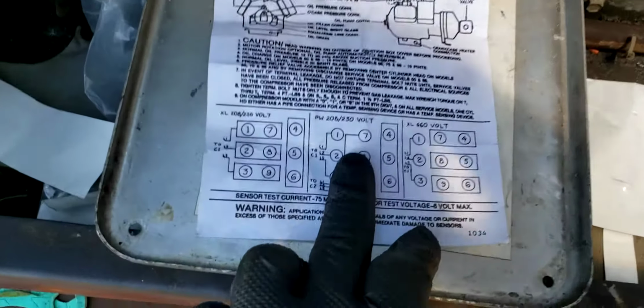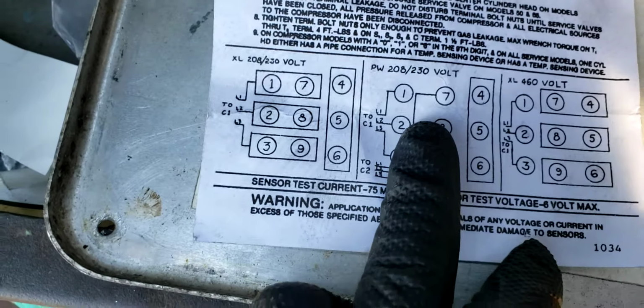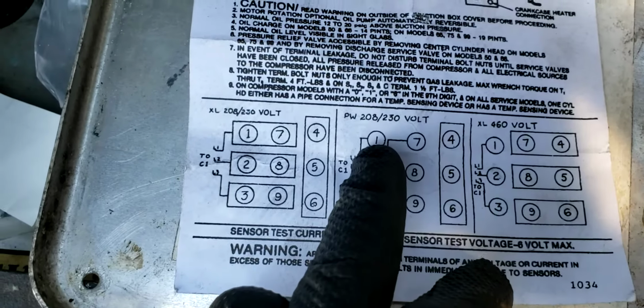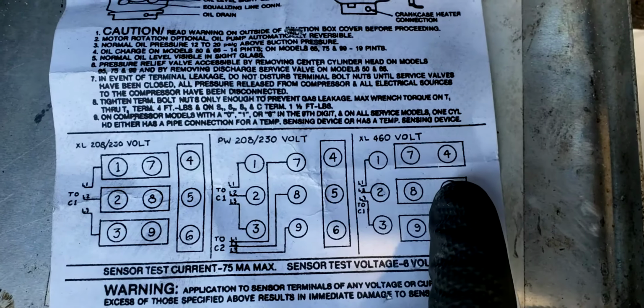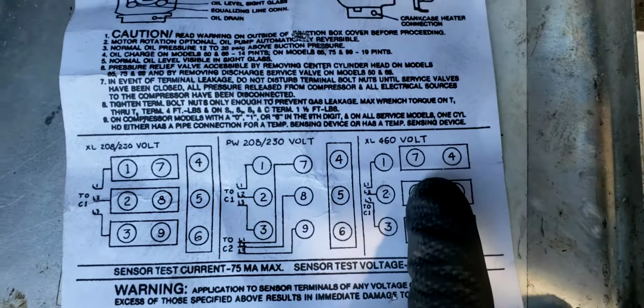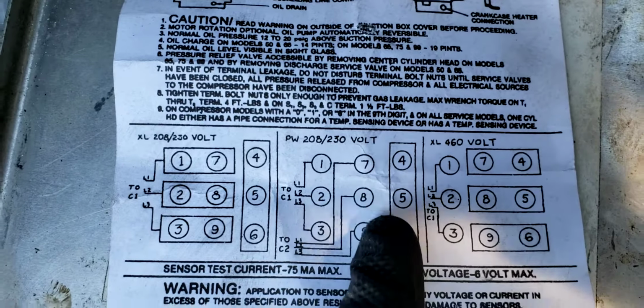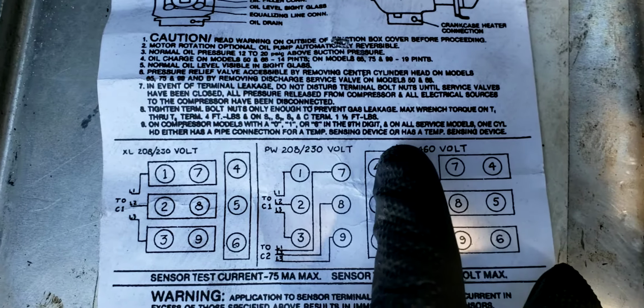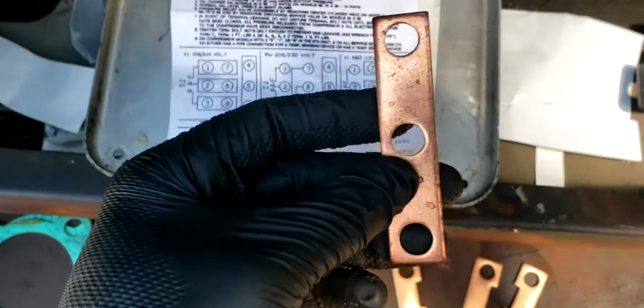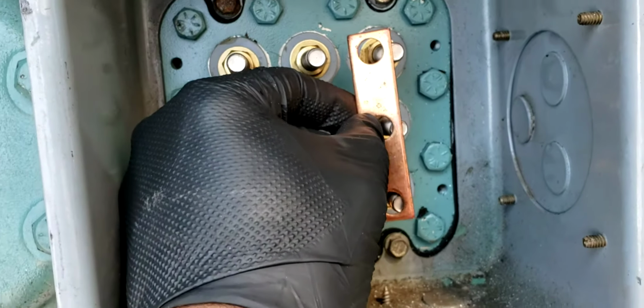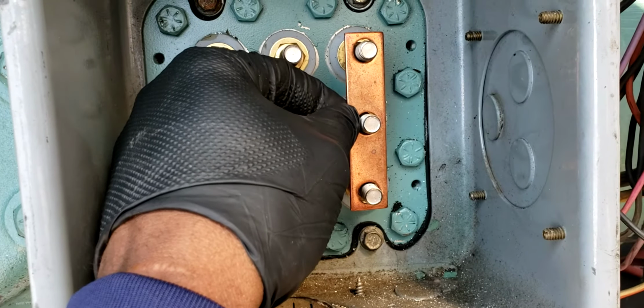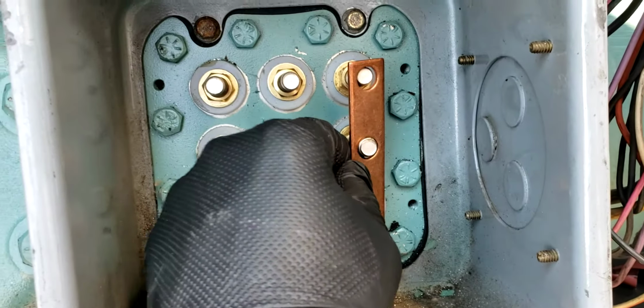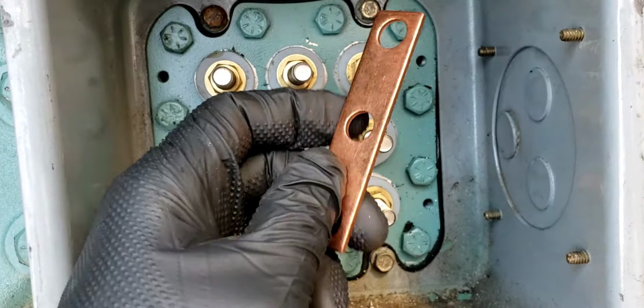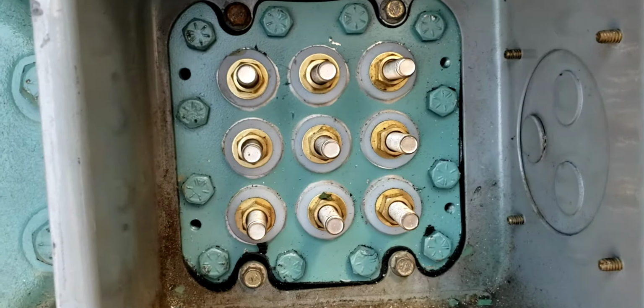This right here in the middle, you're doing part winding, and part winding is only available if you're using low voltage. For 460 or high voltage, it's only across the line. Here's the part winding setup. So what you'll see, 4, 5, and 6 is shunted with this one piece right here. That's where you put that if you're doing part winding start for low voltage.